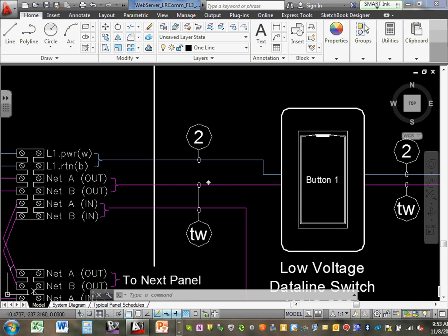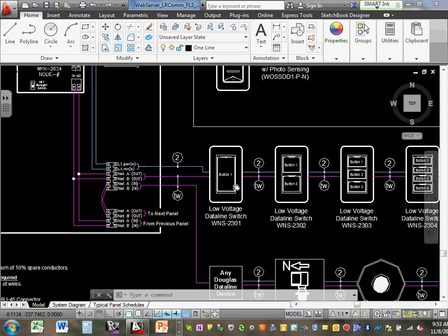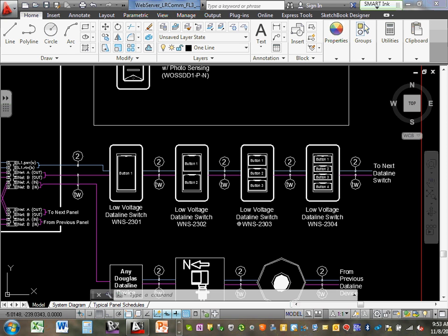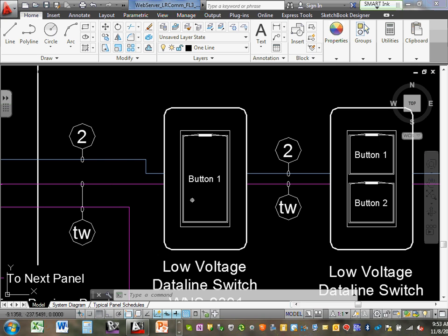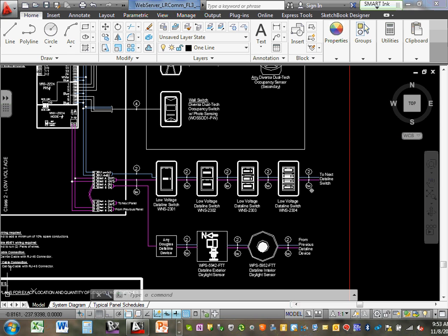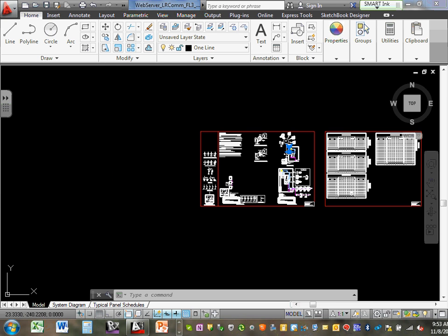So these guys blow up, and now I've got a button station that I need. You're doing that on purpose? No. No. That tells me that I need to have 2 conductors to that single button station, right? So it's a really simple riser. A lot of folks are using this, a lot of design firms are using this because it gets their point across very straightforwardly. Whether you're using all those devices, whether you're tying the occupancy sensor to the system or you're not tying it to the system, and that's all editable, of course, because it's just an AutoCAD. It's your drawing once you download it, right? If you can scroll over to the far right, here we go, over here into the schedules.